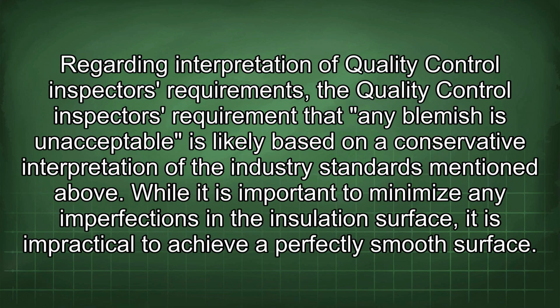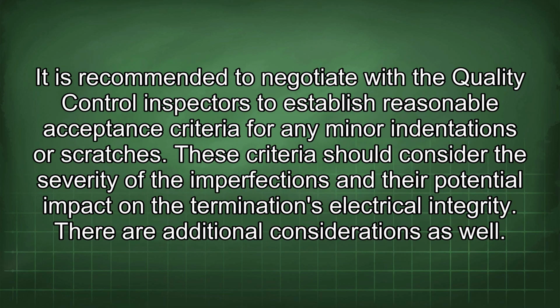Regarding interpretation of quality control inspectors' requirements, the quality control inspector's requirement that any blemish is unacceptable is likely based on a conservative interpretation of the industry standards mentioned above. While it is important to minimize any imperfections in the insulation surface, it is impractical to achieve a perfectly smooth surface. It is recommended to negotiate with the quality control inspectors to establish reasonable acceptance criteria for any minor indentations or scratches. These criteria should consider the severity of the imperfections and their potential impact on the termination's electrical integrity.